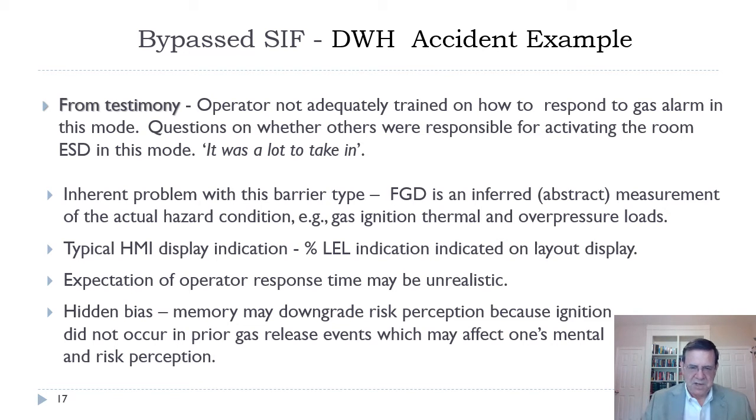And now there's another problem that I don't think is very well recognized in our industry. If I have a SIF type where the detection information is essentially an inferred measurement of the actual risk, there's an inherent problem with that. On a flammable gas detection, the operator is getting percent LEL. The actual risk is the gas ignites, and I have a temperature load or an overpressure load on a receptor.